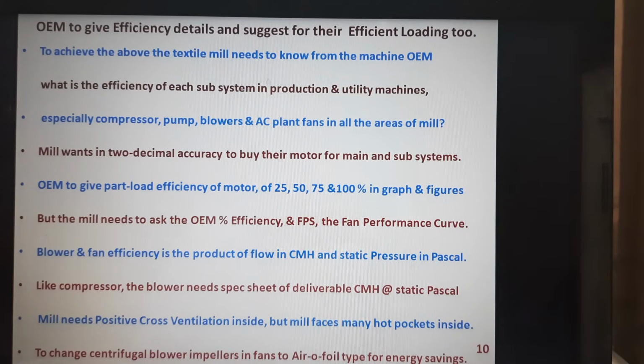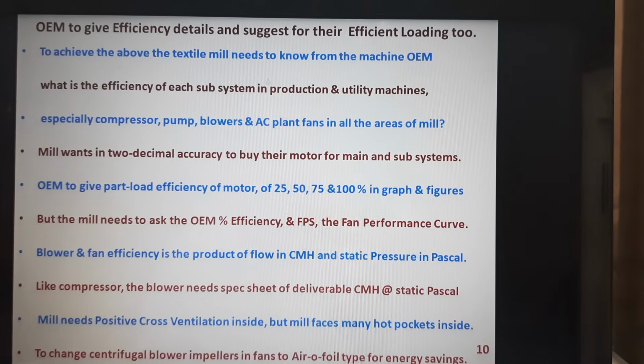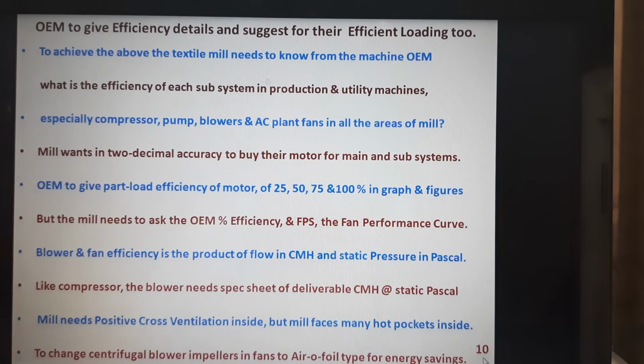So, let us see that positive cross ventilation is maintained inside the mill, and all the centrifugal blower impellers that we are using in the mill, either in the pneumafil or in the WRS or in the comber or in the compact, whatever it may be, need to be aerofoil. See, we have tried this aerofoil impeller application in our pneumafil, and it gave an excellent saving of around 20%. This is always possible in all the other blowers in the mill, and till now the mills have not concentrated on replacing their impellers with energy efficient impellers. It is a welcome change that needs to be done as such.